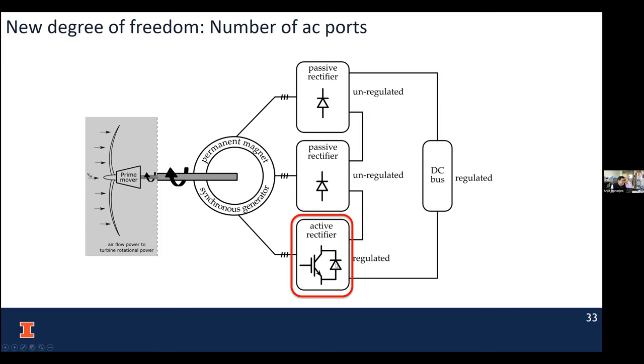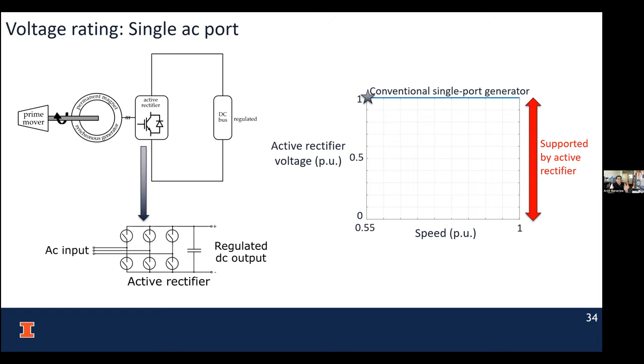Let's go through some details, starting with a conventional system. Before we get started, I'll restrict the operating speed range of the wind turbine from 0.55 to 1. This is very standard for doubly fed machines where we are reducing the power electronics, and this speed range is good enough. The primary reason is that the power you extract from a wind turbine is proportional to the cube of the rotational speed for a direct drive system. So at half speed, 0.55 per unit, you're at only about 10% of rated power. It's pretty much okay to operate within this limited speed range, and we will exploit this feature, as you'll see in a moment.